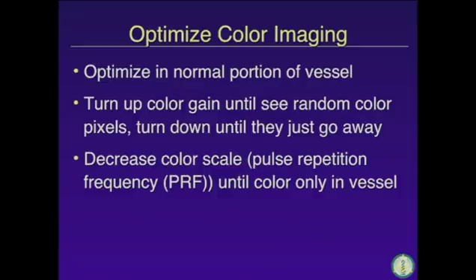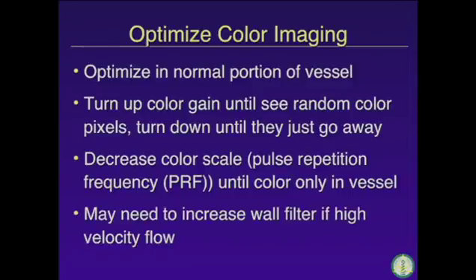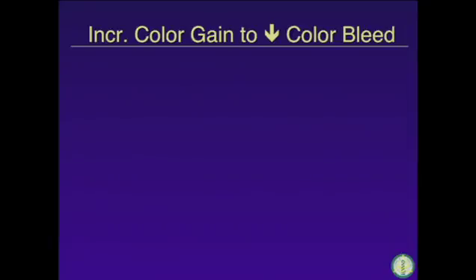Then you need to decrease the color scale, the pulse repetition frequency, until you see color only in the vessel, so you don't have that bleeding of the color pixels into the intima, media, and adventitia of the vessel, or even beyond. You may need to increase the wall filter if there's high velocity flow, so that you have less clutter. It takes out the low velocity signals and you end up with a lot better image if it's a high velocity flow, such as in the aorta.